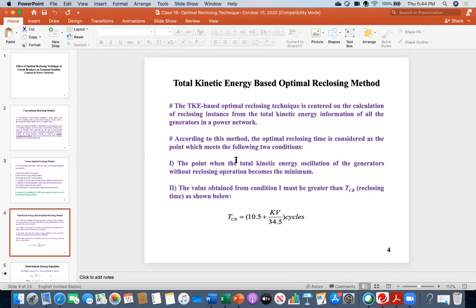So you have to look at the total kinetic energy response that you will be calculating by getting the speed signal from all the generators connected to the network. And then you will be noticing whether that total kinetic energy signal is meeting these two points. What is the first point? The point when the total kinetic energy oscillations of the generator without reclosing operation becomes the minimum. Then it says the value obtained from condition 1 must be greater than TCB, the reclosing time, as shown below.